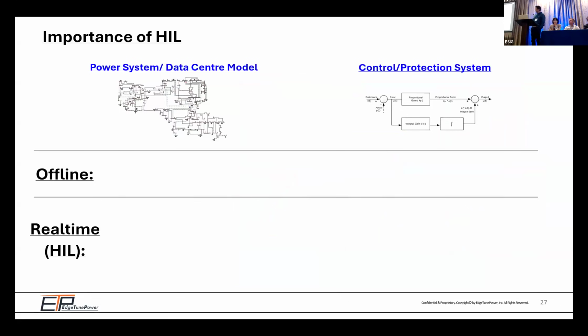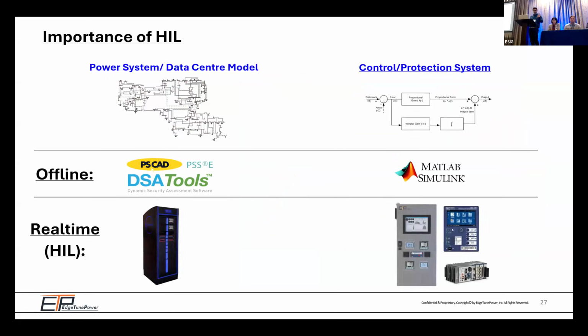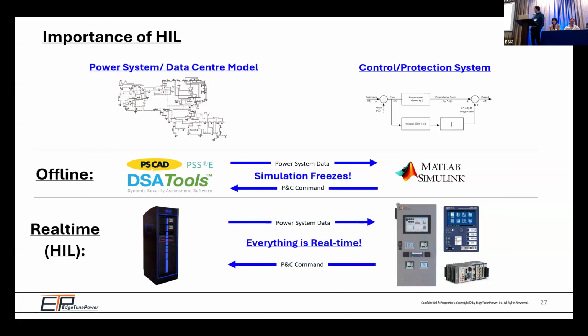I have to speed up a little bit here. So if I want to further shed light on the difference between offline simulation and real-time hardware in the loop testing, let's say you have the model of your data center and you have your controller protection scheme which should be under test. In offline simulation, when you exchange information between your simulation environment and the control system, time freezes, right? Because you want to exchange information between them. But in reality, that's not the case. Otherwise, I would age less. So you cannot freeze the time, unfortunately. So when you exchange data between the real-time simulator and the devices under test, everything is real-time. You cannot stop the clock from ticking, right?